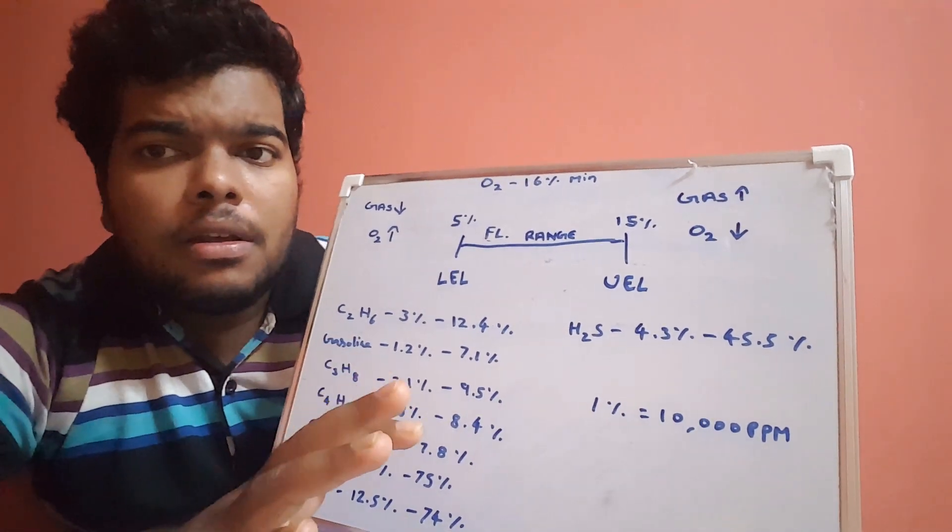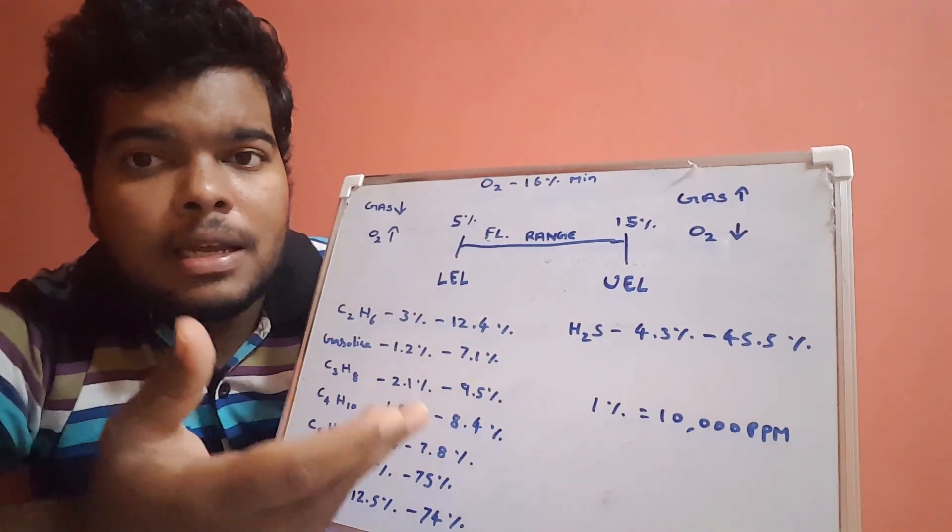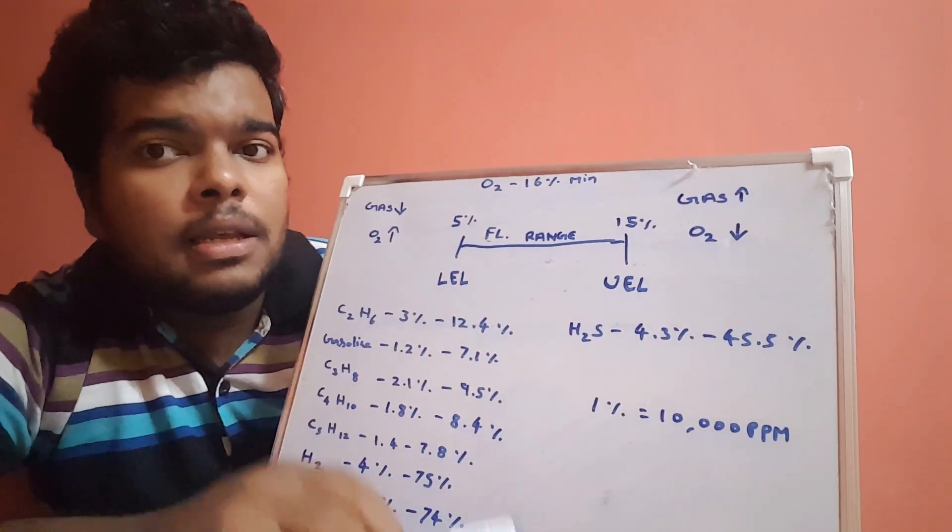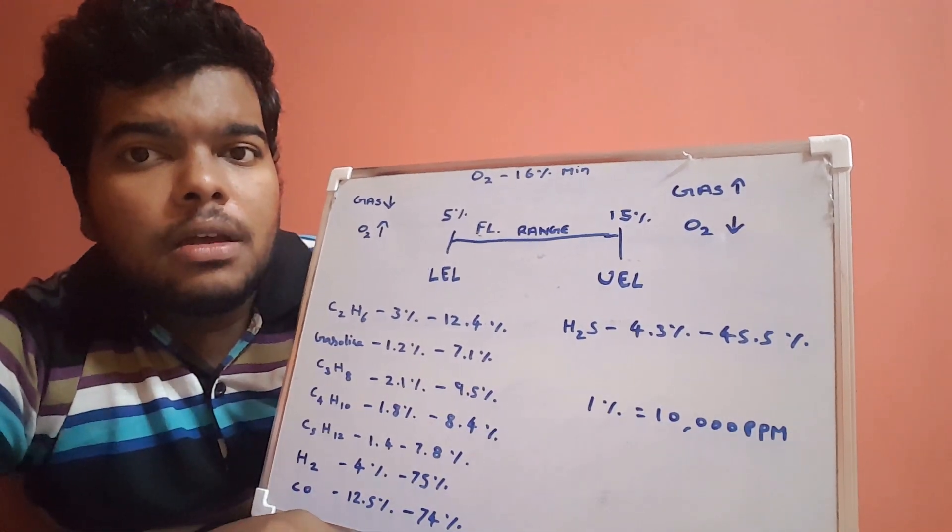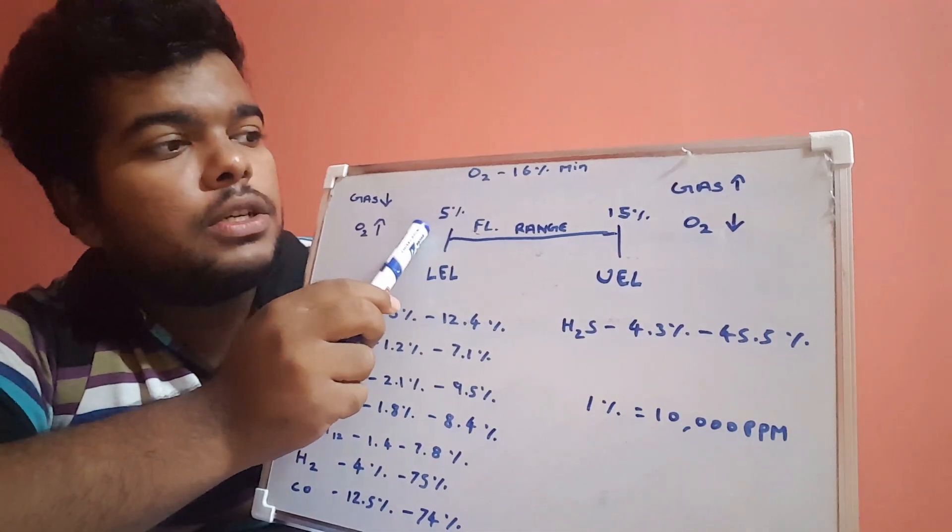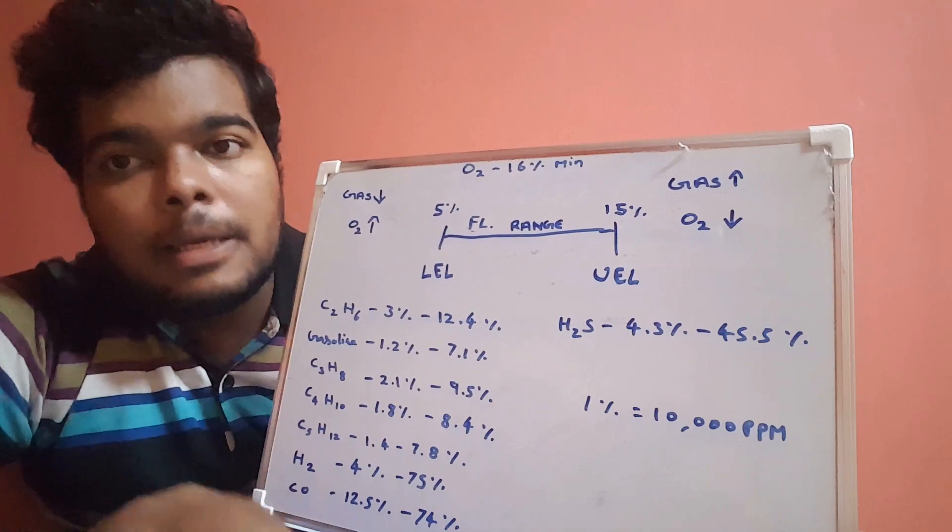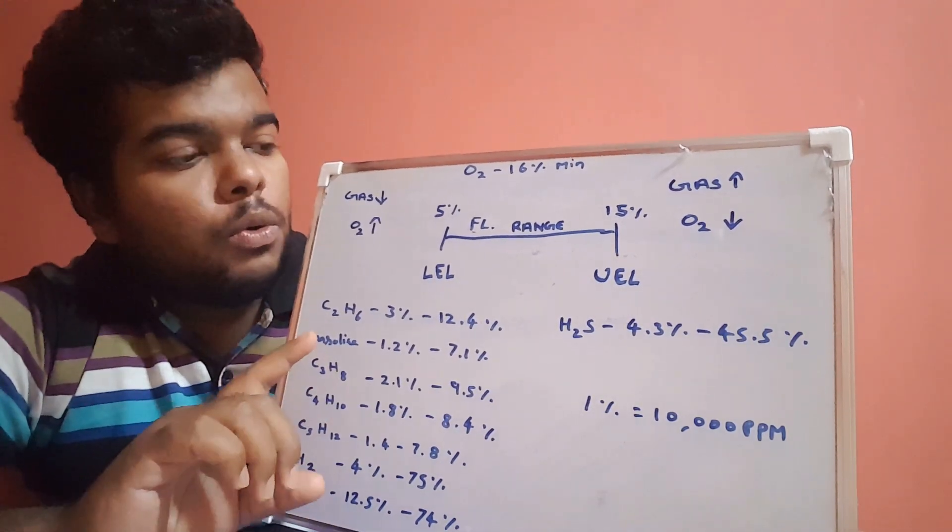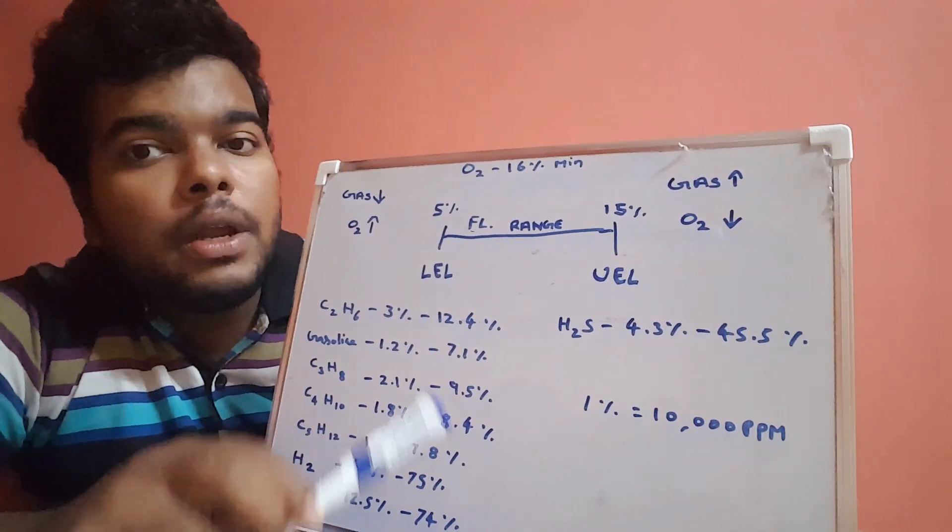They have taken the reference of methane. The LEL value will be measured from 5 percentage to 15 percentage, which is the UEL value of methane. Up to 5 percentage, the alarm will not give.